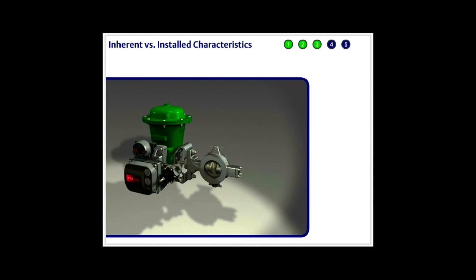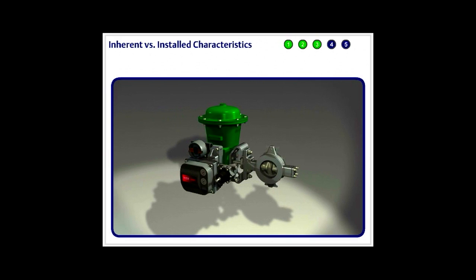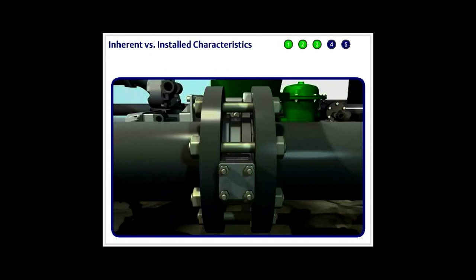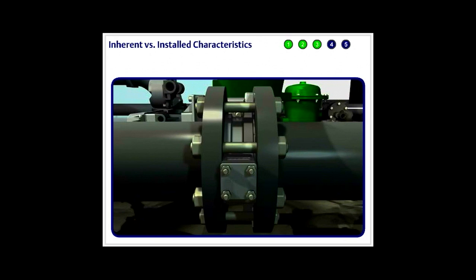A control valve has an inherent flow characteristic and an installed flow characteristic. Understanding the difference between the two is an essential step in achieving good process control. The control disc has an inherent equal percentage flow characteristic that is represented graphically by this exponential curve.